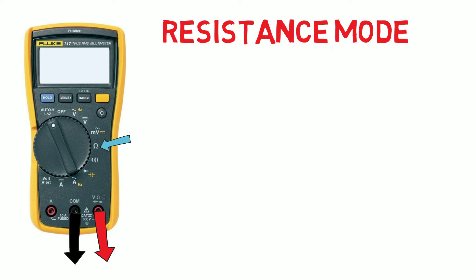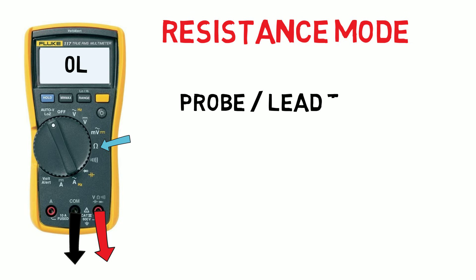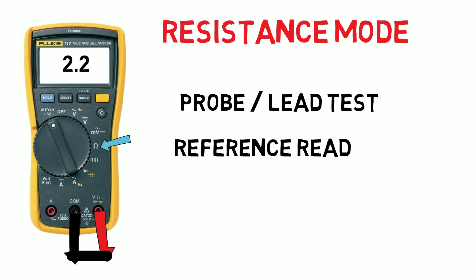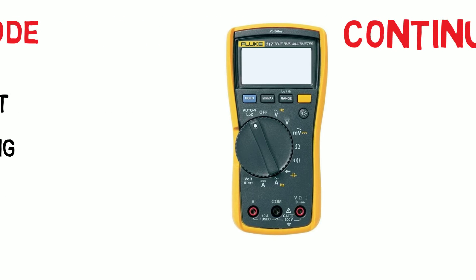If you were to look at the readout you will see the resistance reading is showing open circuit. To test the meter is functioning correctly and that our lead fuses have not blown, a quick continuity test is useful — connect the probe ends together. The meter display should read a small ohms value of around two or three ohms, which is the resistance of the test lead. It is useful to take this reading as a reference as the resistance will need to be subtracted from any part of a circuit you test.